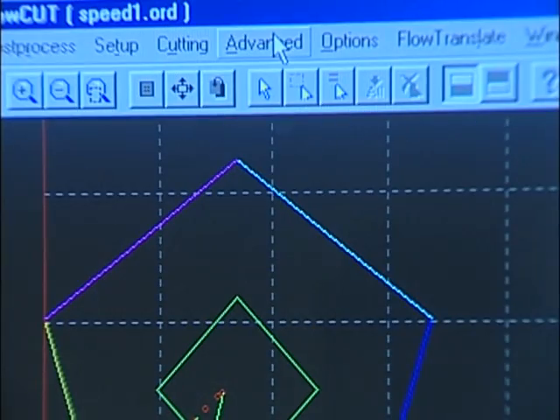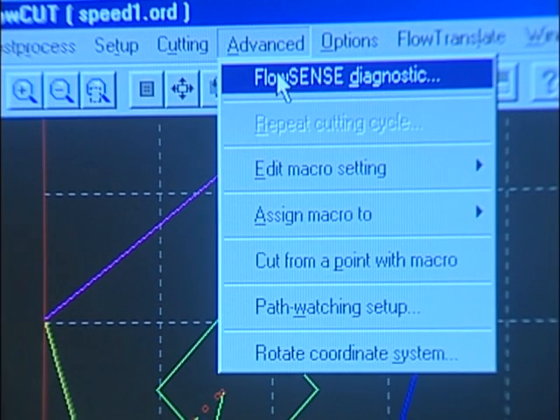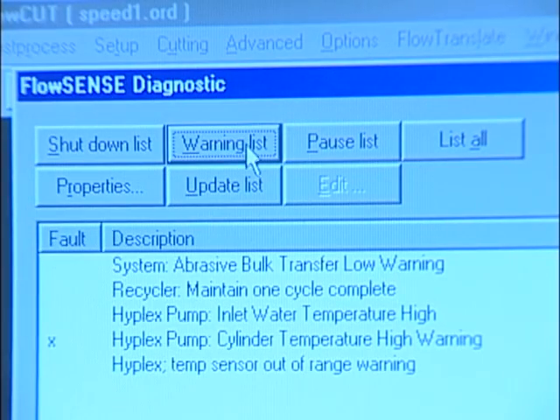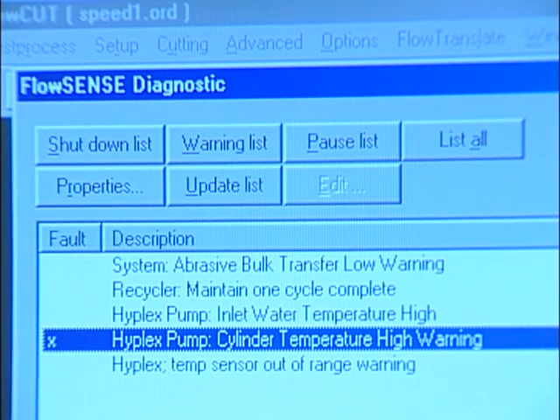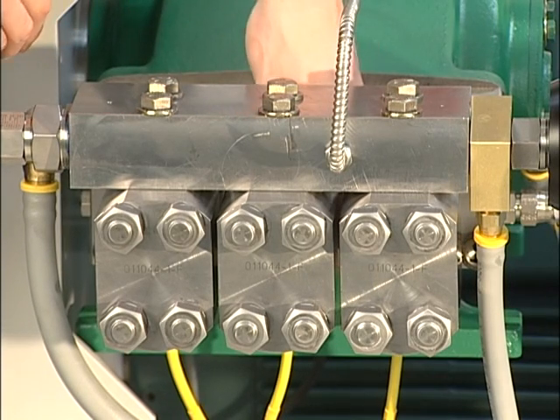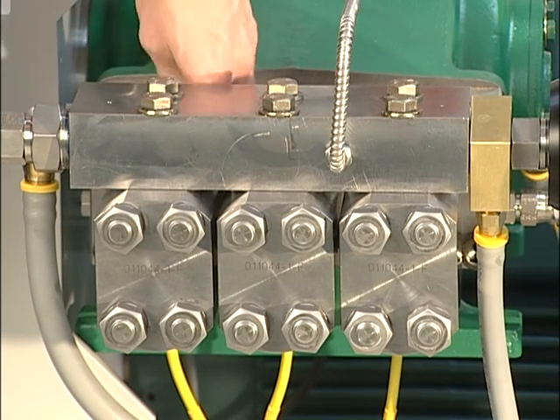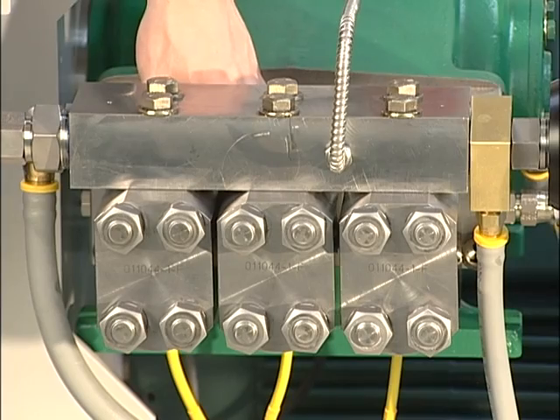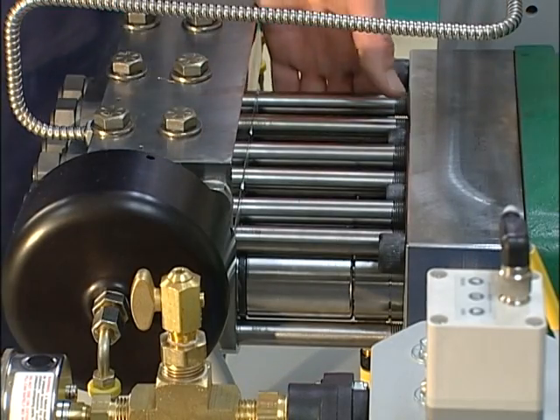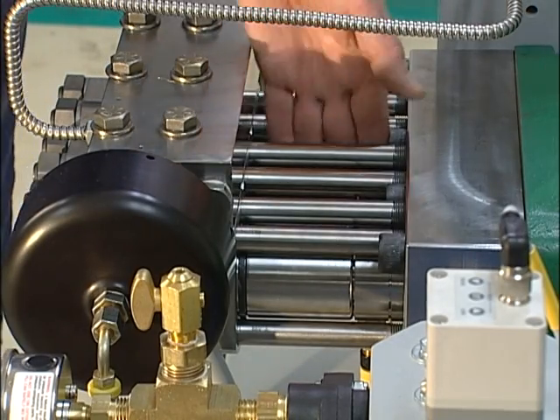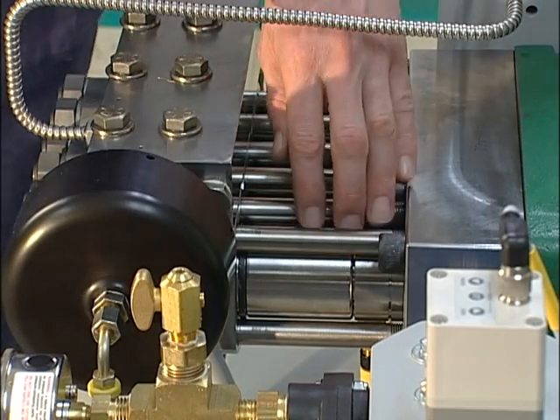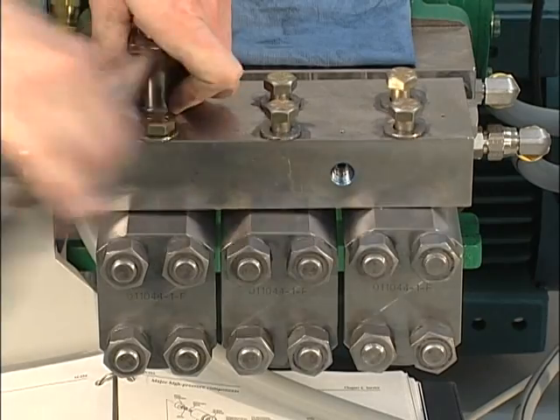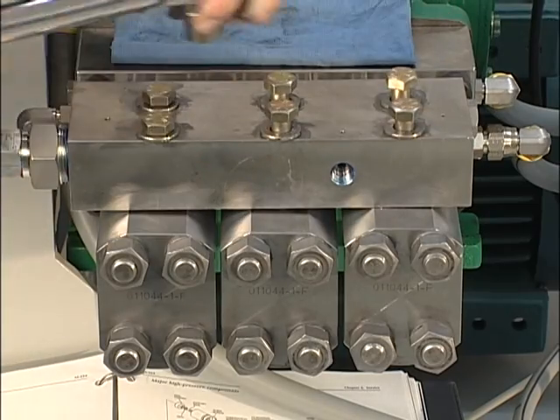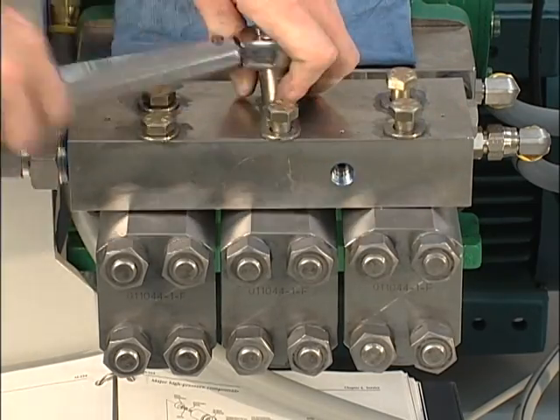All scheduled service intervals should be performed as preventive maintenance. If trouble reveals poor pump performance, or if the pump fails in between any of the service intervals, you must judge whether to correct the individual problem or to perform the complete service procedure. Generally, if the trouble occurs within 50 hours of a scheduled service interval, a complete service procedure is performed. If the complete procedure is performed prior to the scheduled interval, ensure that the next interval is scheduled at the appropriate interval from the time of repair.